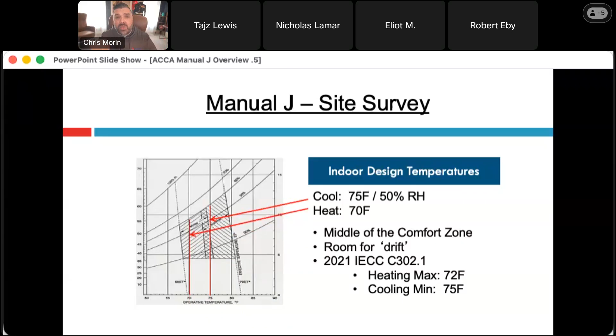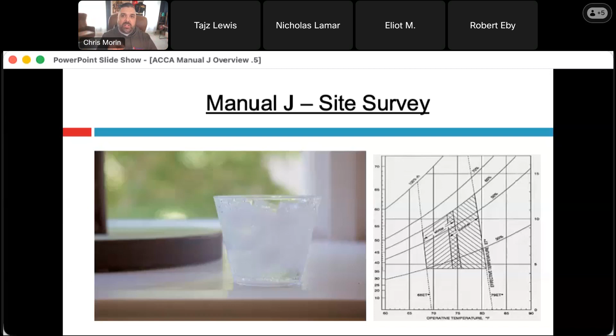Also, which is really important for your climate in Austin, if we run the system too cold, it is quite possible we're going to change the properties of that air to where a device that shouldn't be below the dew point of the air reaches that. And we would end up getting moisture on the inside of windows or inside building cavities. And obviously, when it's cold, dark, and wet, that creates the four-letter M word that I'm not going to mention on the recording here. So really important. We want to stay within those design conditions so that we don't bring building materials below dew points as well. All right. So it's really important that we look at the health and safety reason for those design temps on top of comfort. All right.